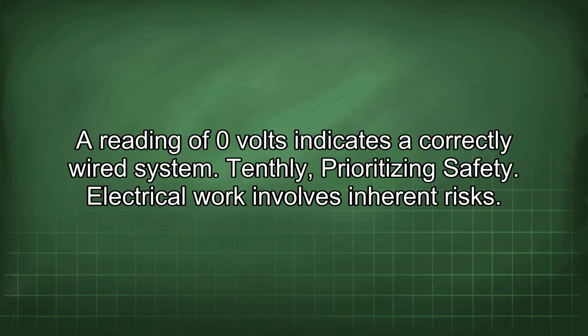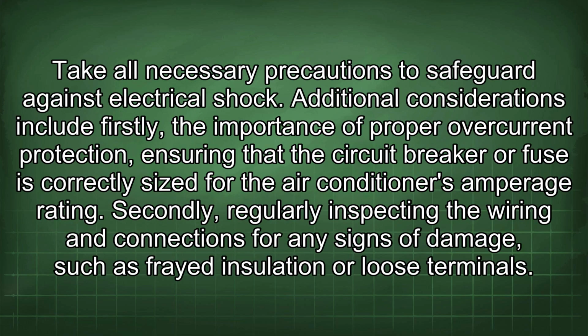Tenthly, prioritizing safety. Electrical work involves inherent risks. Take all necessary precautions to safeguard against electrical shock. Additional considerations include, firstly, the importance of proper overcurrent protection, ensuring that the circuit breaker or fuse is correctly sized for the air conditioner's amperage rating. Secondly, regularly inspecting the wiring and connections for any signs of damage such as frayed insulation or loose terminals.